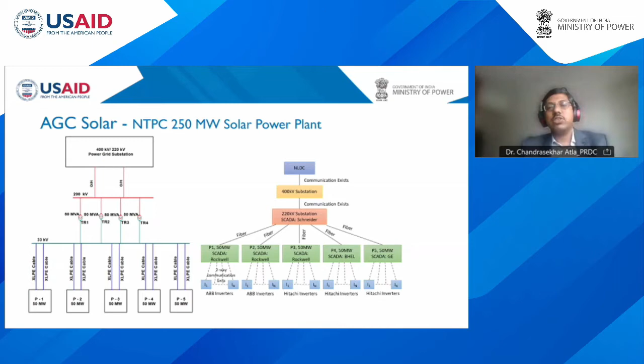If you see the right-hand side, the AGC aggregator has been placed at one of the blocks at the NTPC solar power plant location, that is the P3 block, 50 megawatt. As per this scope, we implemented the AGC for 4 blocks: P1, P2, P3, and P5. All blocks earlier had one-way communication. Now we made that two-way communication, and all the logic controls will be taken care of by the AGC aggregator. The AGC aggregator signals pass through the 220 kV and 400 kV substations and reach the NLDC.